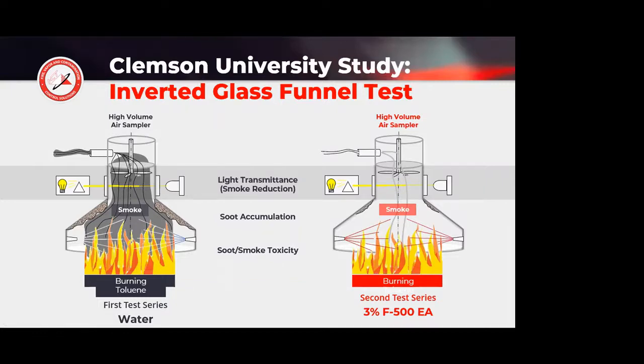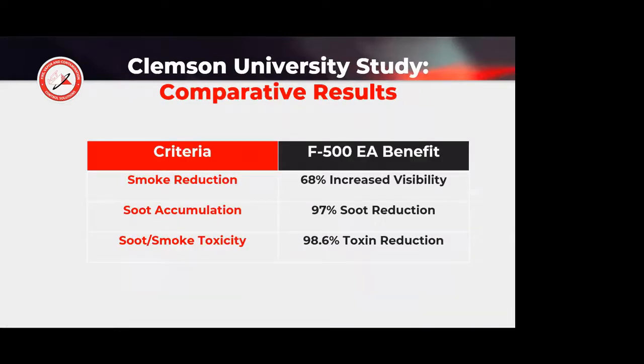So we did 2 different tests. Each test was done 3 times. The first test was just plain water being sprayed through the smoke flume. And again, we looked at the light, looked at this soot accumulation right here on the plenum, and also sampled this soot and looked at the soot and smoke toxicity. So we did 3 tests with plain water, 3 tests with a 3% F500 solution, and these were the results. So we had a smoke reduction of 68%.